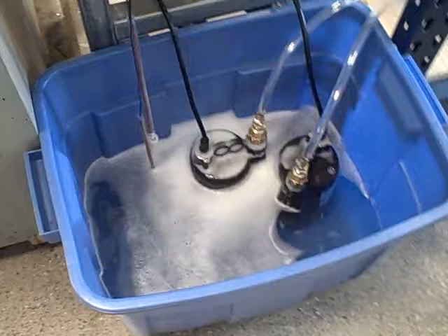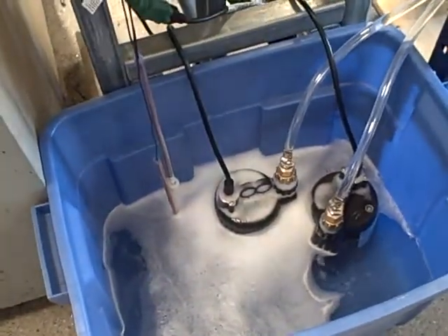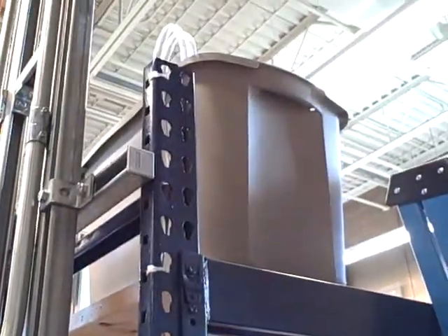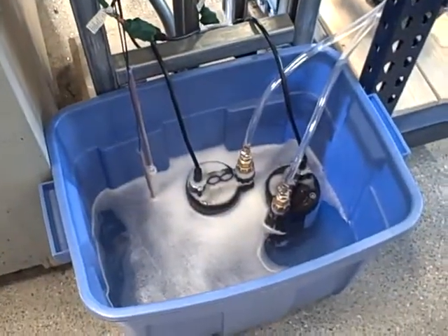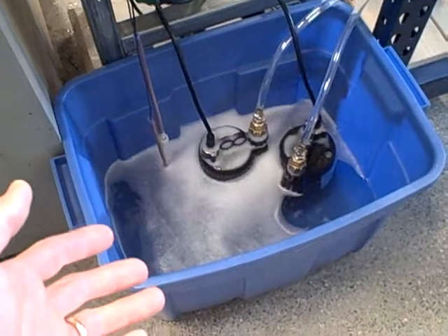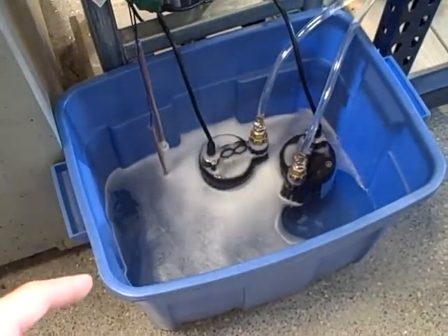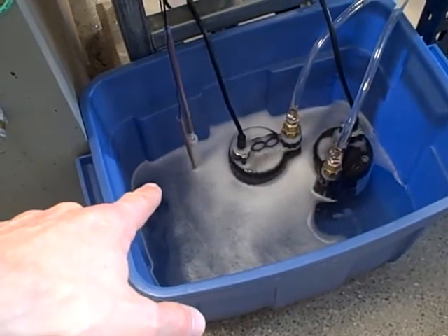The pumps themselves are submersible water pumps located inside this tub, and currently one of them is turned on. It's pumping water out of the tub up into a higher level reservoir. The idea being we are simulating a lift station, as you might see in a wastewater treatment system, where you have a local reservoir or a sump where wastewater runs by gravity from local businesses and homes into the sump, and a pair of level switches monitors the level of the wastewater.